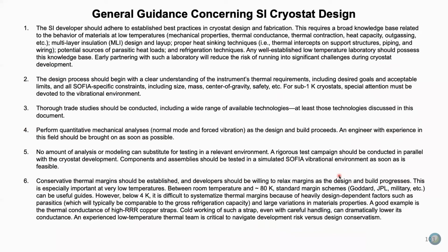Six, conservative thermal margins should be established. The thing about thermal margins at these temperatures is that it's kind of hard to deal with. At higher temperatures, you have standard margin schemes - Goddard, JPL, the military all have them. But at very low temperatures, it's difficult to systematize thermal margins because of heavily design-dependent factors like parasitics, which can be comparable to the gross refrigeration capacity, and also large variations in material properties, like the thermal conductivity of copper or aluminum.